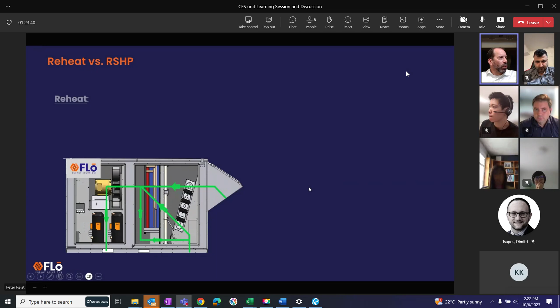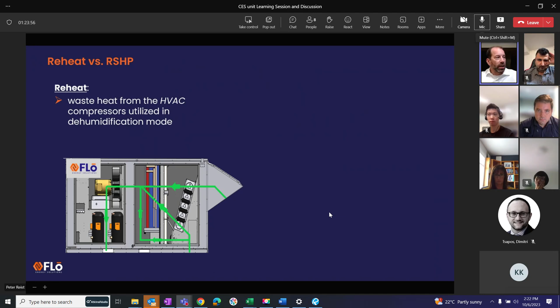Just one thing I want to clarify, the difference between reheat, and I heard Jerome mention reheat at the beginning of the presentation. Reheat is when we get waste heat from our own compressors as an HVAC unit and use that to temper our dehumidified air, right? And it only happens when we're doing dehumidification because our compressor is running. Whereas when we're talking about a refrigeration source heat pump, or what we were calling reclaim, it's waste heat from the refrigeration unit's compressors. And so we get it year round. We get it for dehumidification and we get it for heating. And so it's a great source of heat. It's way more heat than we generate, and we can use it for year-round operation. So this is why we are so happy about that.